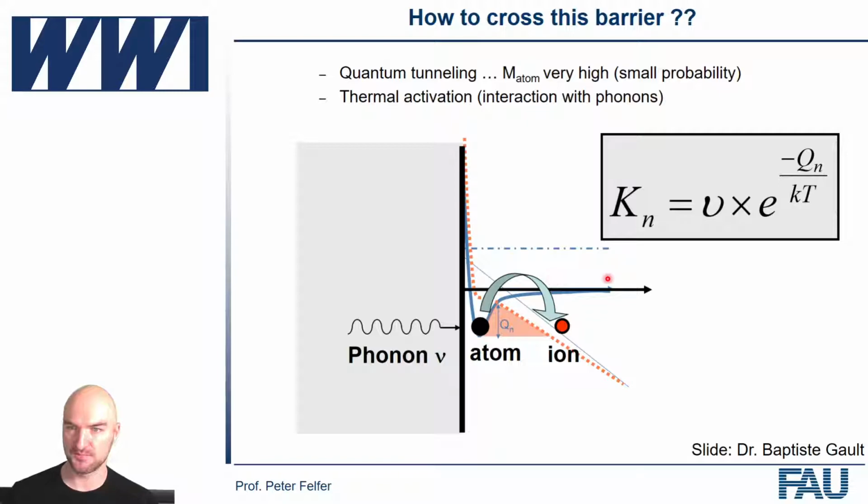But the very important takeaway is that we can adjust the height of this evaporation barrier by adjusting the field. And the field, as I said earlier, is essentially just voltage divided by specimen radius. Or if you have a specimen of a particular radius, it's just proportional to your voltage. And your voltage is just a knob on your instrument. If you build your own instrument, maybe it's not that obvious on a commercial instrument, but if you build your own instrument, it's literally just a knob that you can twiddle, you can play with.